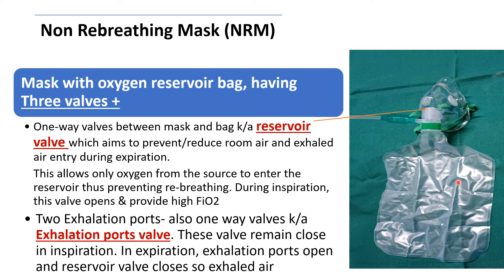This bag is connected to the oxygen source via oxygen tubing. When the reservoir valve is closed during exhalation, oxygen from the source fills the reservoir bag. This valve allows only oxygen from the source to enter the reservoir bag, thus preventing rebreathing. During inspiration, this valve opens to provide high FiO2.